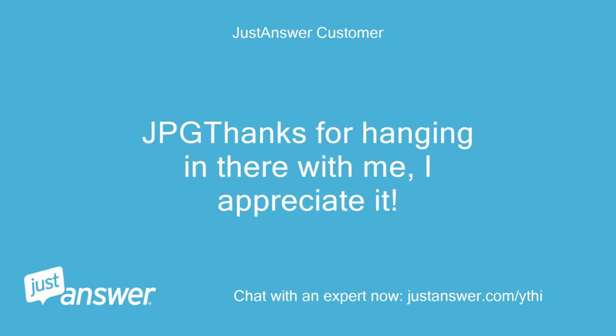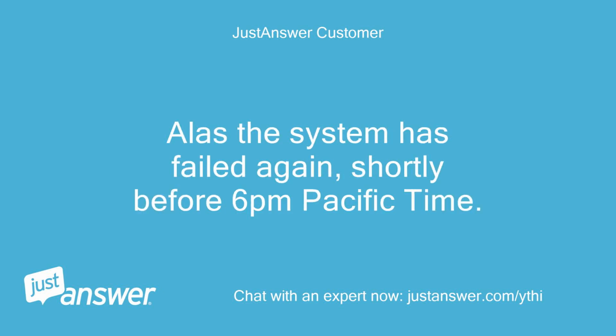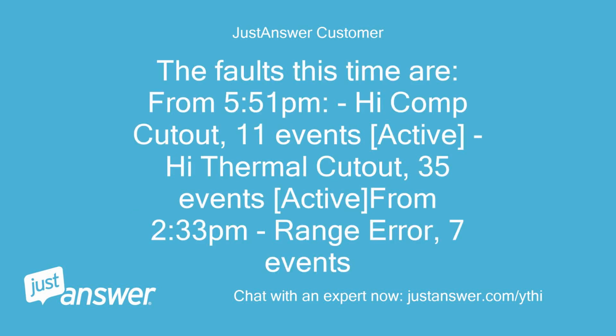Thanks for hanging in there with me, I appreciate it. Alas, the system has failed again, shortly before 6 p.m. Pacific Time. The faults this time are, from 5:51 p.m., high comp cutout, 11 events, active; high thermal cutout, 35 events, active; and from 2:33 p.m., range error, 7 events.